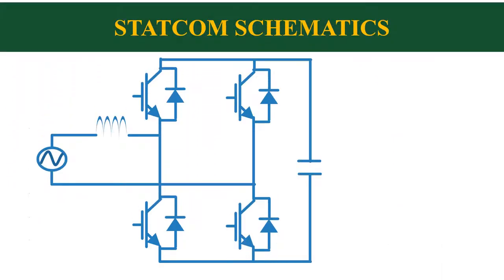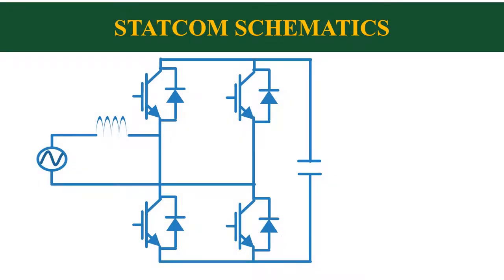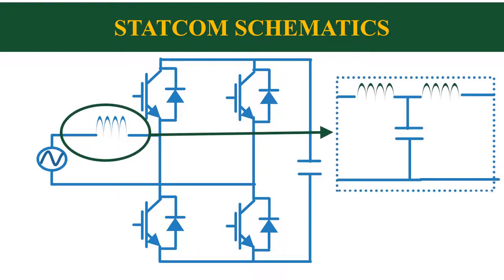This is the basic structure of a single phase Statcom. It consists of a voltage source inverter used to convert the DC input voltage to AC output voltage. The inverter can be realized using any power electronic devices such as MOSFET, IGBT, etc. A capacitor is used at the input to supply a constant voltage to the inverter. An inductor is used at the grid side for the filtering of high frequency components in the current generated by the inverter. Instead of L-filter, we can also use an LCL filter for better filtering performance.